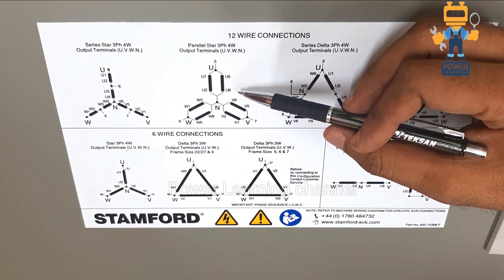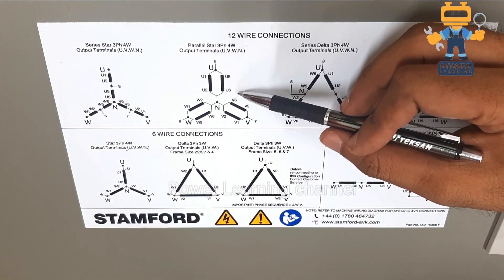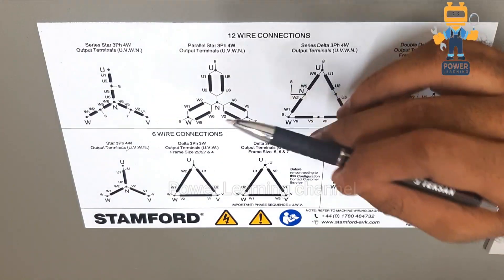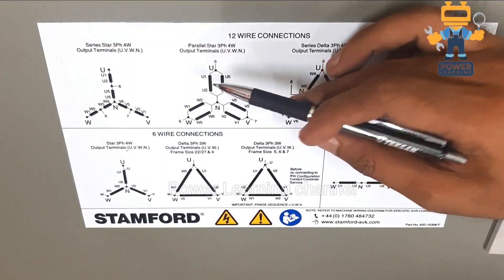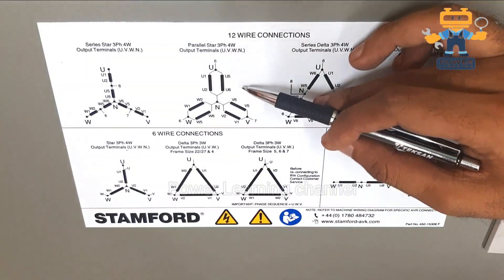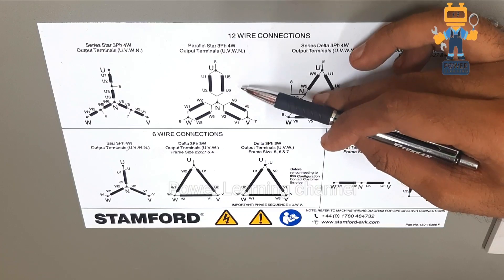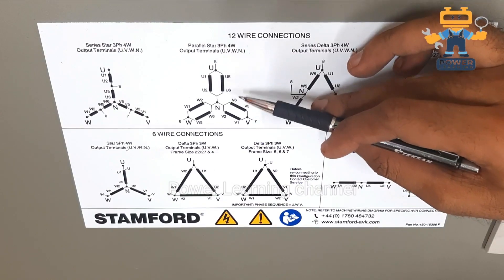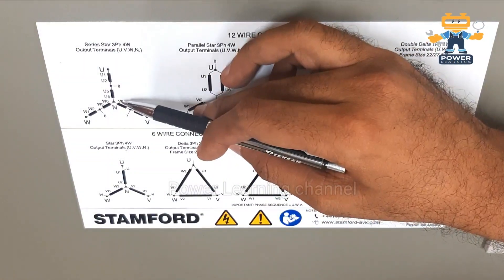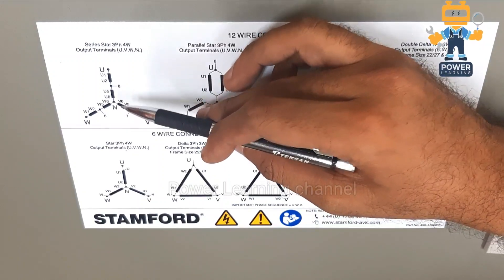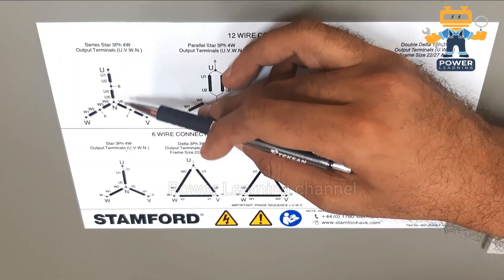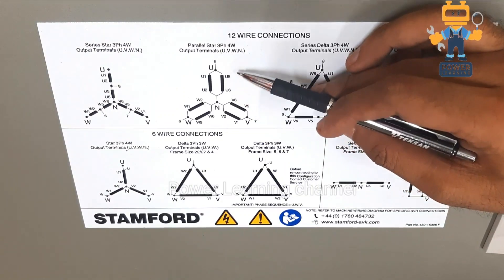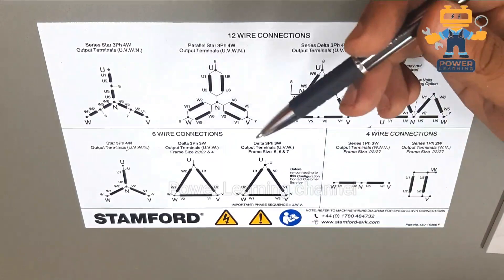When using the low-voltage parallel star configuration, we get 127 volts line to neutral and 220 volts line to line. Once you need to convert your alternator from a 380V to a 220V three-phase system, you have to use parallel star. Parallel star produces 220/127V; series star produces 380V, with a maximum rating up to 480V line to line.